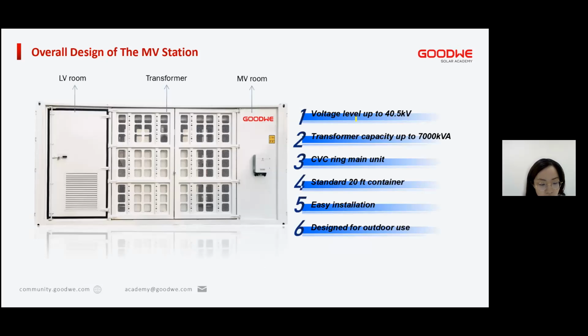Okay, next let's look at the MV stations. Here you can see our overall design for the MV station. The structure is very simple. It consists of an LV room, and in the middle there's a transformer, and on the right-hand side there's the MV room. Our MV station was designed to have a voltage level up to 40.5 kV, and the transformer capacity is up to 7,000 kVA.